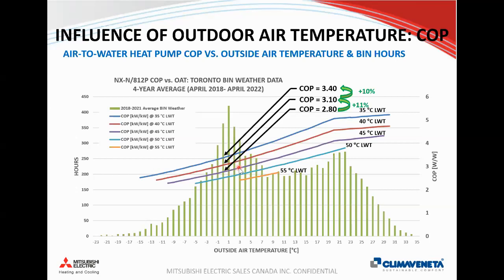Just one point on this: if you're doing design or looking at different systems, using a lower water temperature usually requires different types of heat emitters, maybe more expensive heat emitters designed specifically for low temperature applications, like low temperature panels. So don't discount it too soon. You need to look at the operating costs and the increase in efficiency that you'll get with a lower temperature. Not only that, but you're also going to be able to use this all the time down to -15, which is going to cover 99% of the operating hours. The operating expense savings should actually counteract the additional first cost of heat emitters.